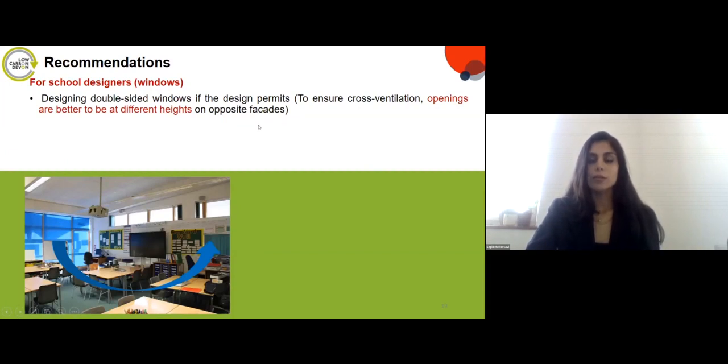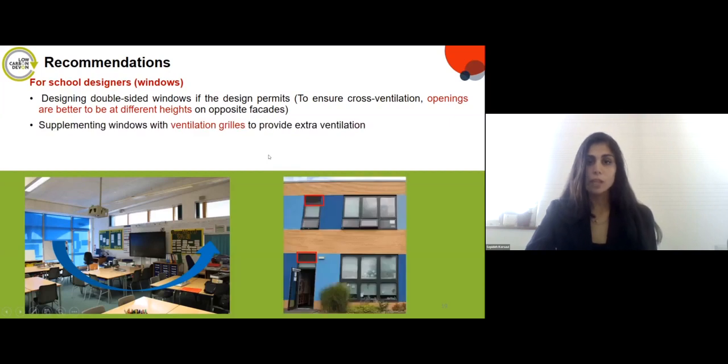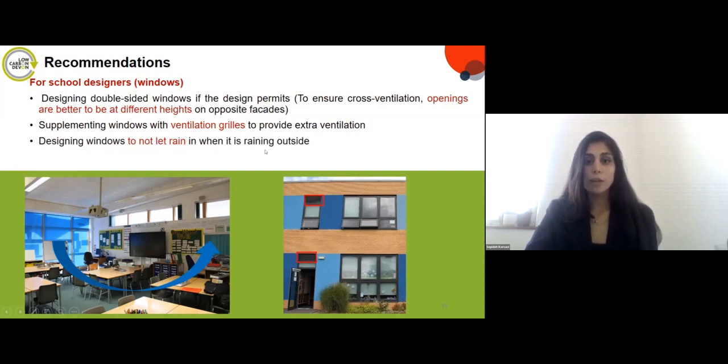Regarding double-sided classrooms, where design permits windows on two sides, it's important to position windows at different heights on opposite facades to facilitate cross ventilation. Ventilation rates can also be supplemented with ventilation grilles to provide extra ventilation. Since rain was a factor limiting window operation, windows should also be designed to prevent rain ingress when open.